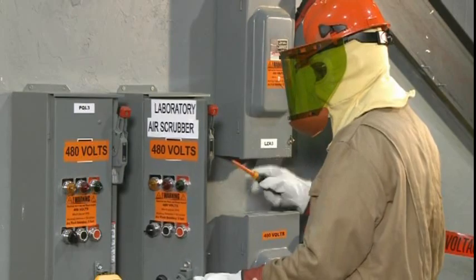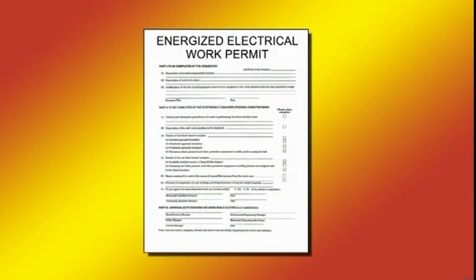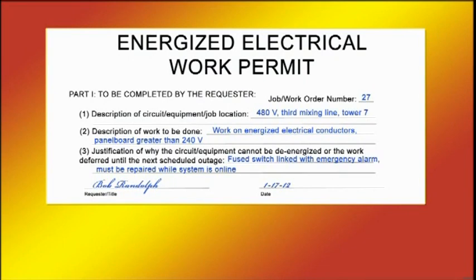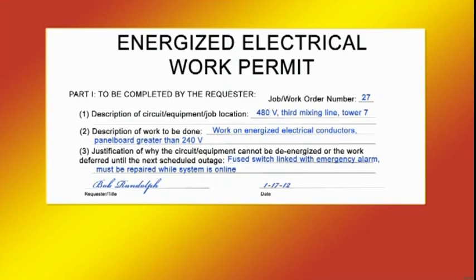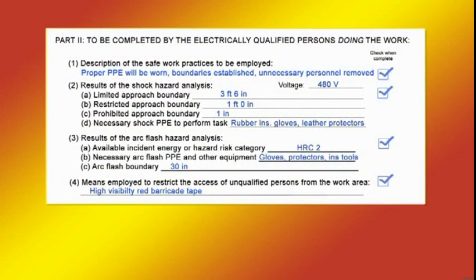The energized work permit will include, but is not limited to, the following information: a description of the circuit and equipment to be worked on, as well as their location, justification for why the work must be performed in an energized condition, a description of the safe work practices to be employed, the results of a shock hazard analysis, which includes the voltage to which workers will be exposed, and a description of required shock protection equipment and approach boundaries. The results of an arc flash hazard analysis, which includes a description of required arc flash protective clothing and equipment, as well as the arc flash boundary.